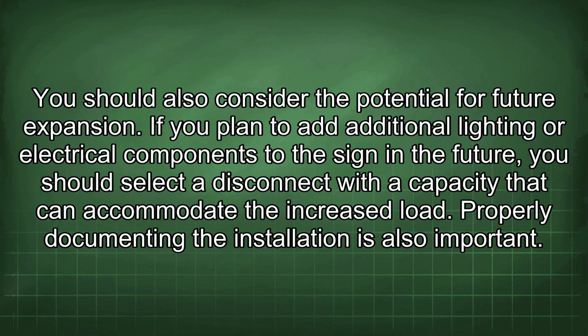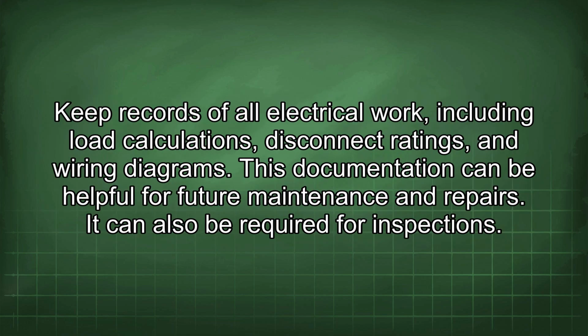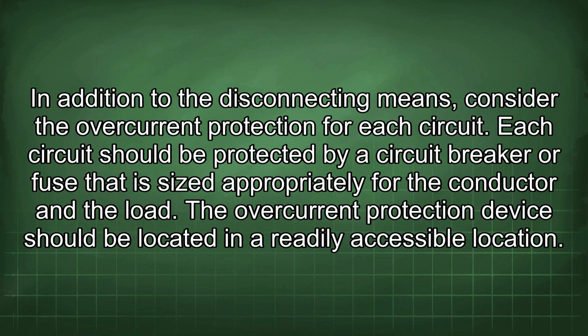Properly documenting the installation is also important. Keep records of all electrical work, including load calculations, disconnect ratings, and wiring diagrams. This documentation can be helpful for future maintenance and repairs. It can also be required for inspections. In addition to the disconnecting means, consider the overcurrent protection for each circuit. Each circuit should be protected by a circuit breaker or fuse that is sized appropriately for the conductor and the load. The overcurrent protection device should be located in a readily accessible location.